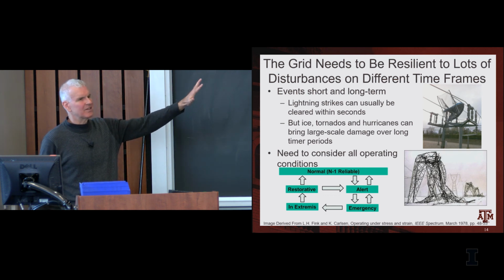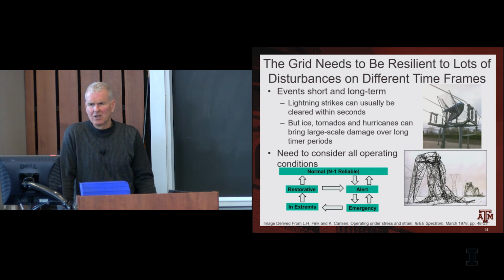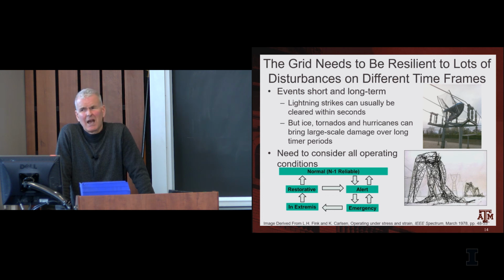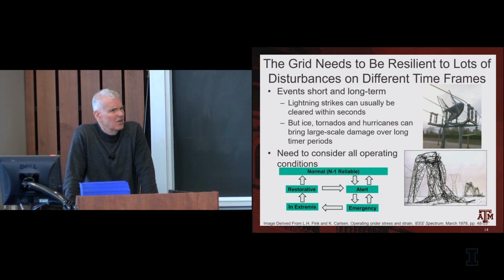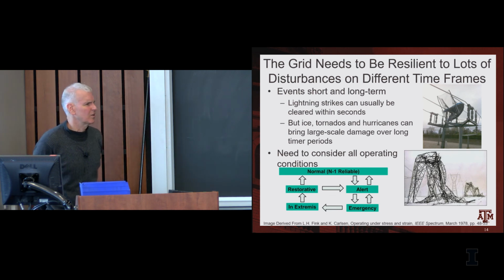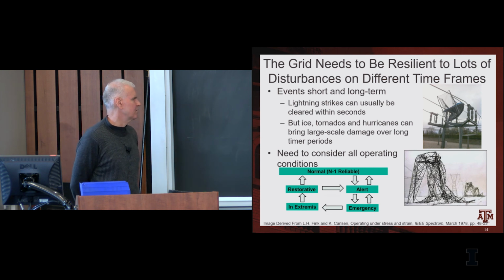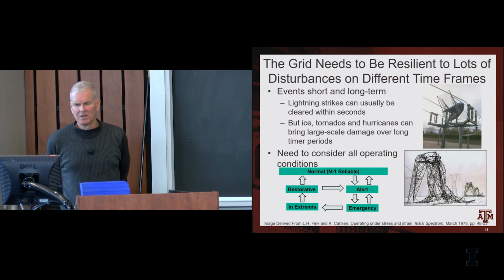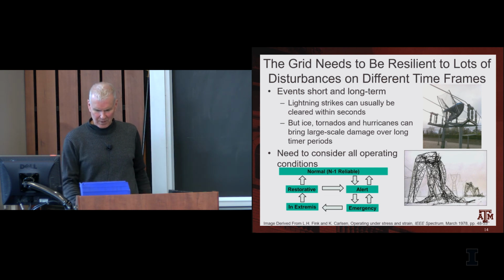In operating the system, we have to take this into account. Usually you're in the normal situation, where the grid is operated so that if any single device fails, you'll be okay. Then something could occur, you lose some devices, and you go into an alert situation, where you're worried about a potential failure. If that failure starts to occur, you go into emergency operation. Eventually you might reach what's called in extremis, where you're in danger of losing a large chunk of the grid—something we saw on August 14th, 2003. If you do lose the grid, you move to restorative, and hopefully get back to normal. These are all things that need to be considered when operating the grid.